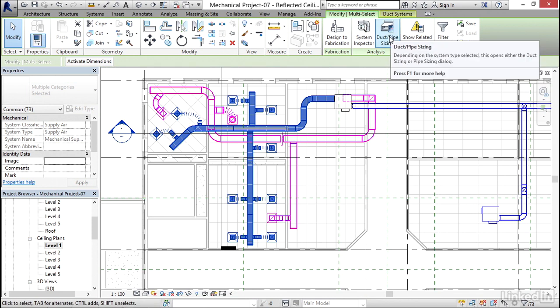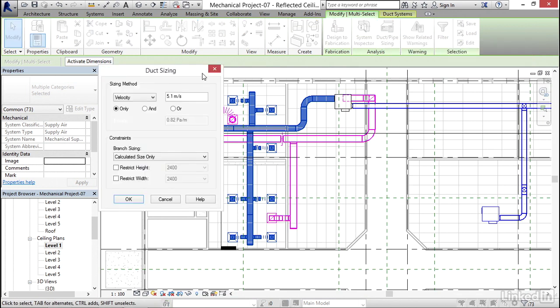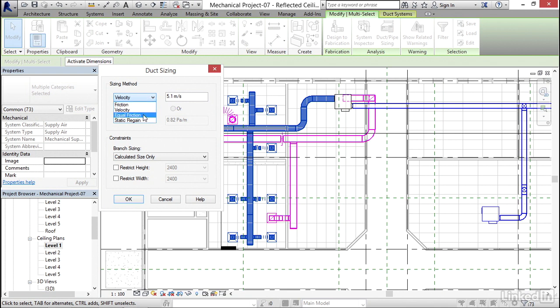Now I'm going to click on duct pipe sizing. My sizing method, I'm going to hit the drop down here. It used to be we could only go on friction. Luckily, now we can do friction, velocity, equal friction, and static regain. I'm going to grab friction.